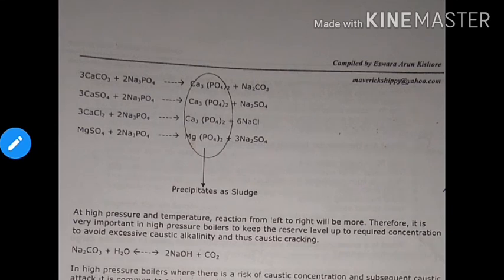If phosphate concentration is very high, it will form calcium phosphate as a sludge precipitate. If sodium phosphate level is very high, it forms a precipitate as sludge in the boiler water. Sodium carbonate is also formed, which reacts with water to form NaOH plus CO₂. So if the phosphate reserve is high, it will form NaOH in the boiler water, increasing the alkalinity level.